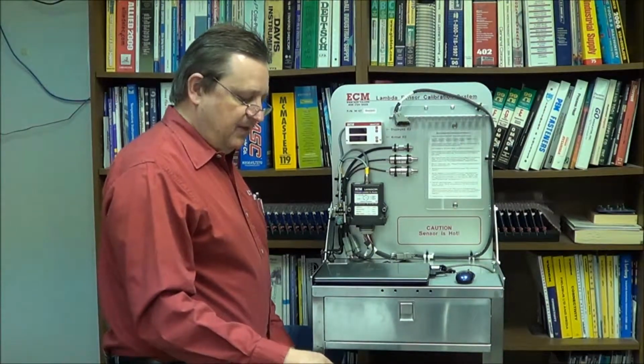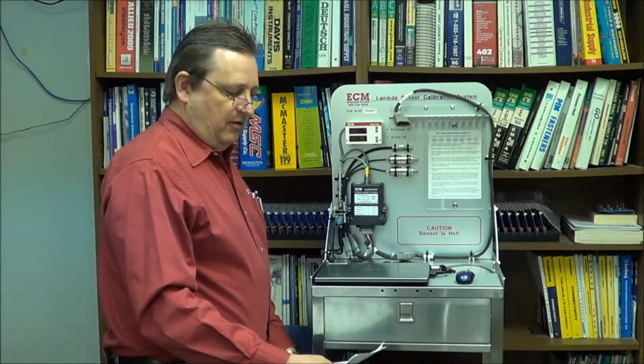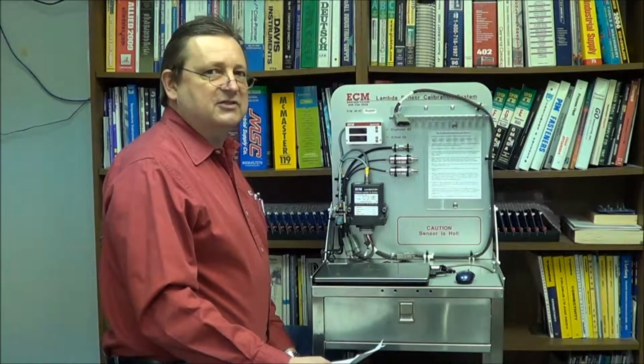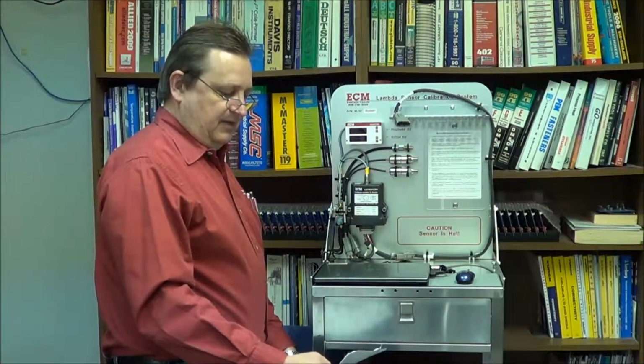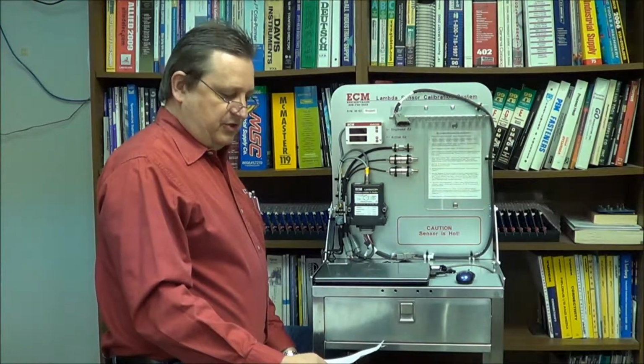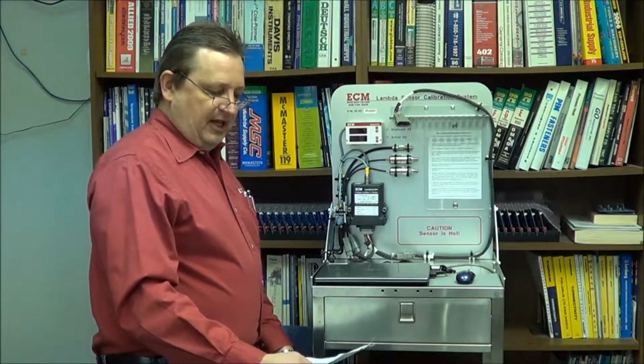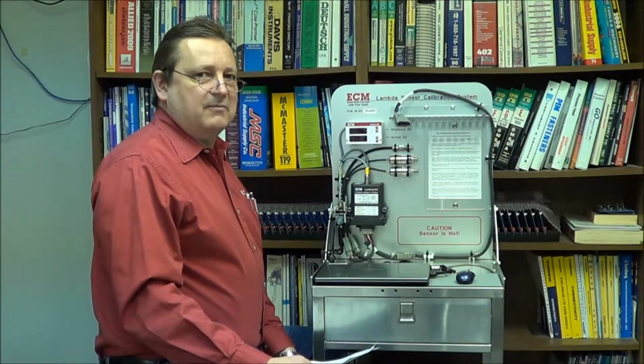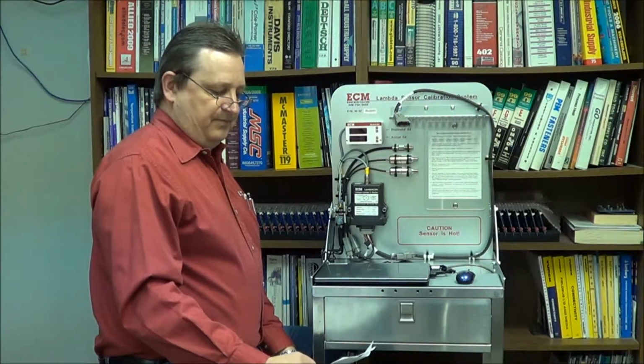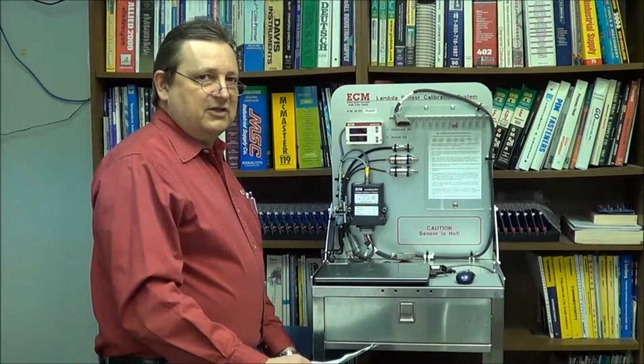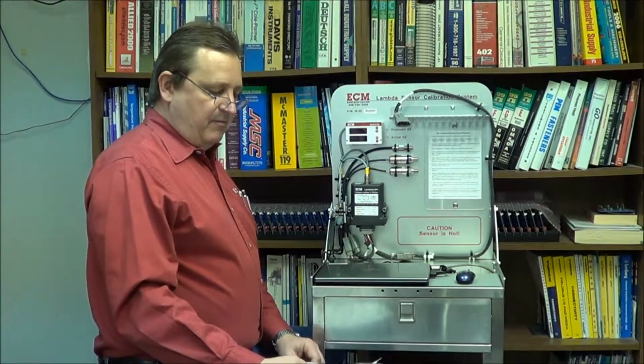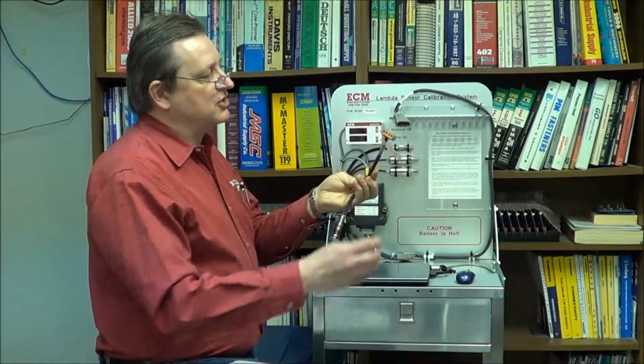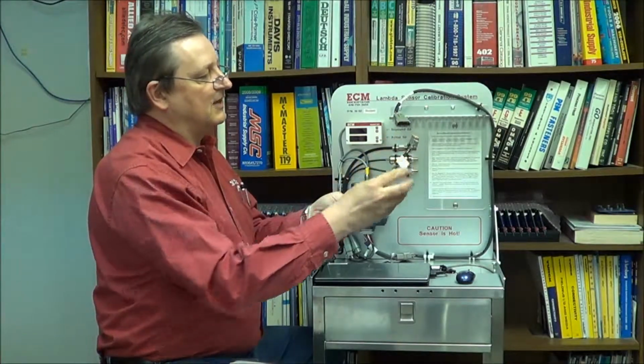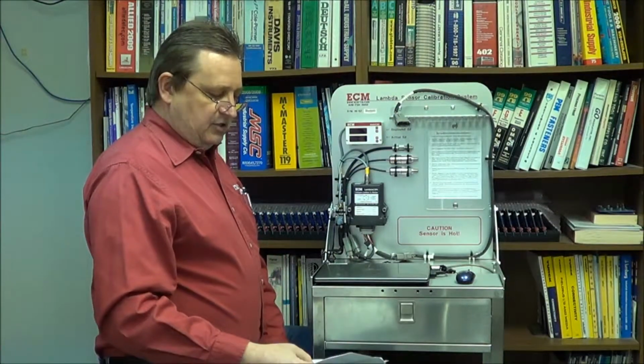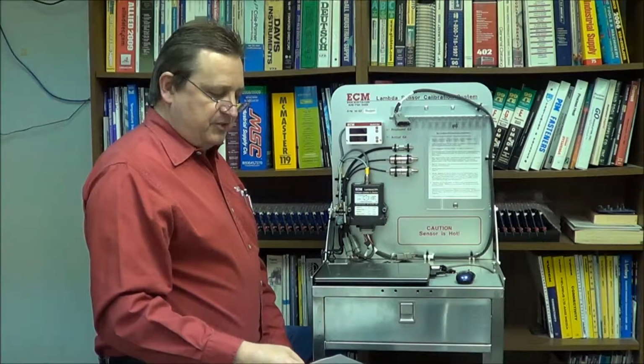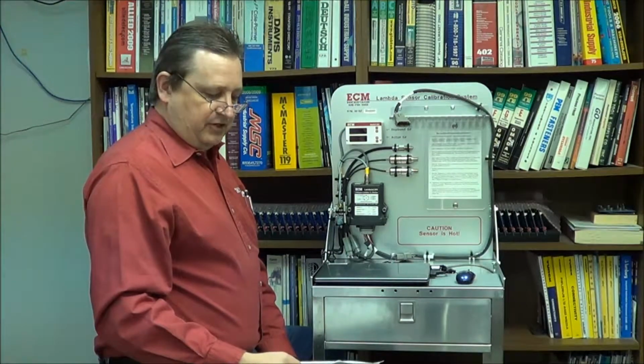I'm with ECM. This video is the tutorial for ECM's Lambda sensor calibration system. The Lambda sensor calibration system is for Lambda sensors used with ECM's analyzers and modules. The sensors used in these analyzers and modules have a memory chip in the Lambda sensor's connector. In this memory chip is stored ECM's factory calibration and your field calibration.